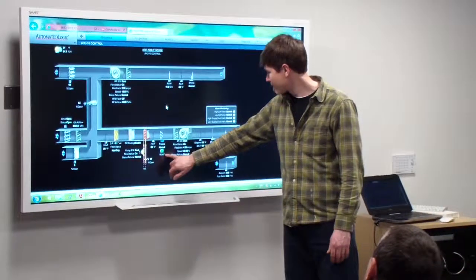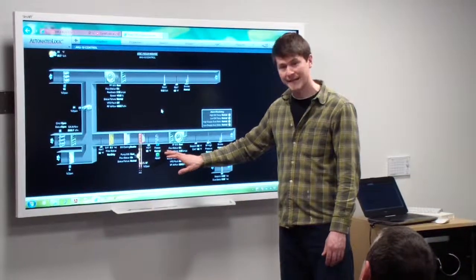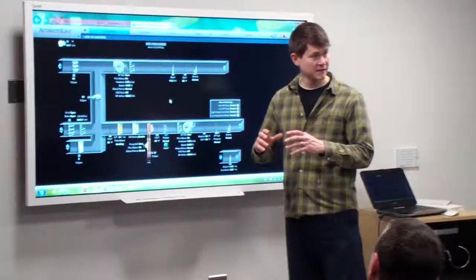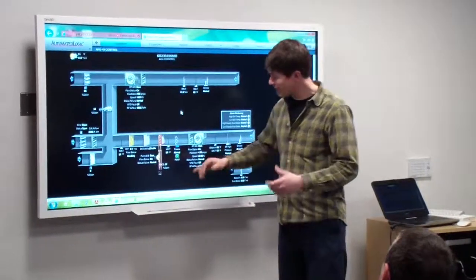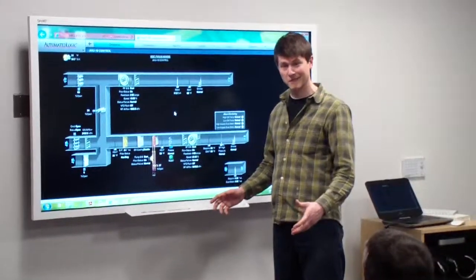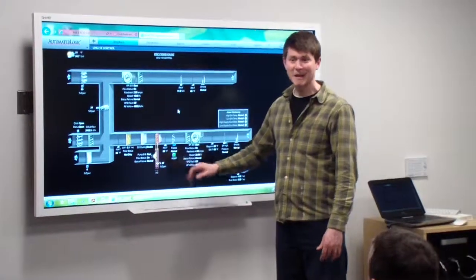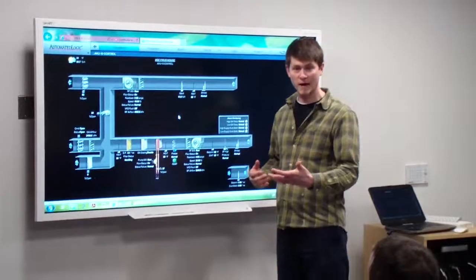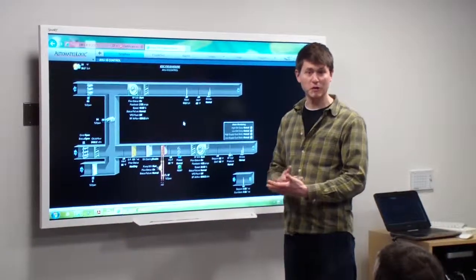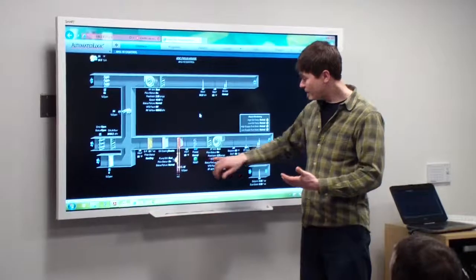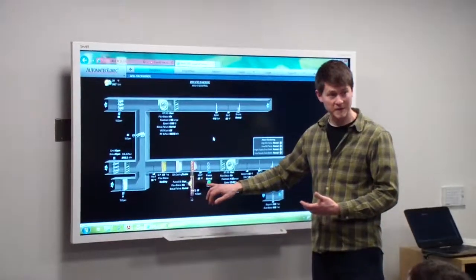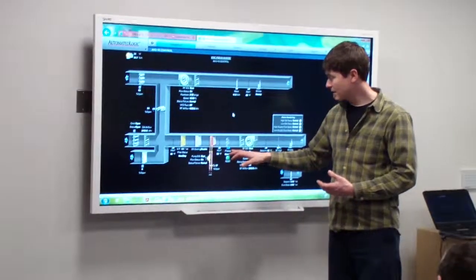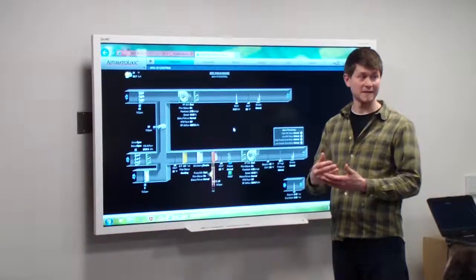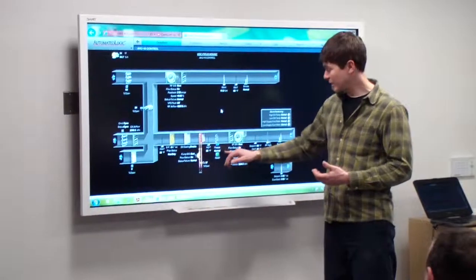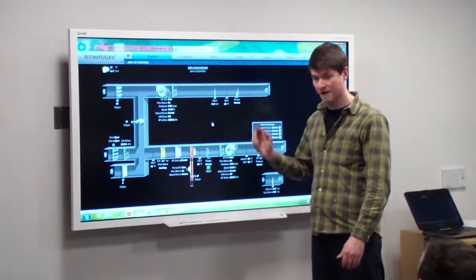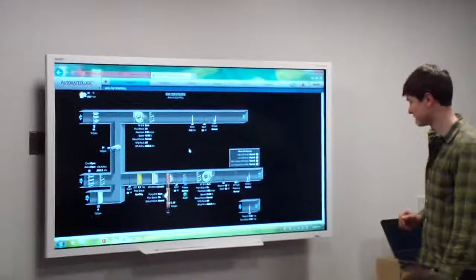And then your freeze stats, which you have a reset on. If this goes into freeze, it's not a manual reset device. It would be wise to go up and take a look at the unit to make sure that nothing's burst before you click this button. But then you would come back to the front end or wherever, if you've got a tablet in front of you or you're looking at it through your cell phone, then you will have to, through software, click this reset button. And then as long as the device itself has actually been cleared, as in it's above 38 degrees, you'll be able to hit that, reset the unit, and then it will start back up to its normal start procedure.